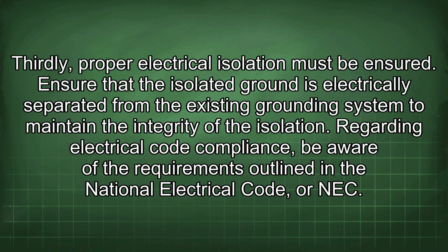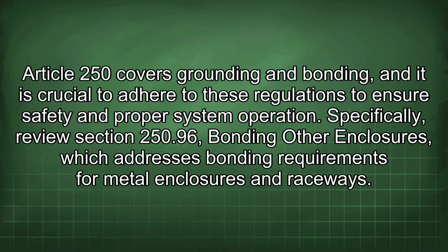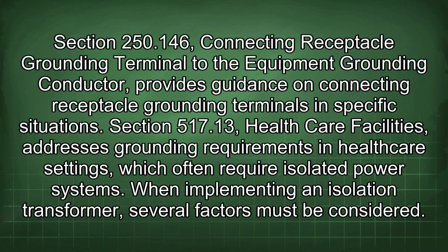Regarding electrical code compliance, be aware of the requirements outlined in the National Electrical Code, or NEC. Article 250 covers grounding and bonding, and it is crucial to adhere to these regulations to ensure safety and proper system operation. Specifically, review Section 250.96 Bonding Other Enclosures, which addresses bonding requirements for metal enclosures and raceways. Section 250.146 Connecting Receptacle Grounding Terminal to the Equipment Grounding Conductor provides guidance on connecting receptacle grounding terminals in specific situations. Section 517.13 Healthcare Facilities addresses grounding requirements in healthcare settings which often require isolated power systems.